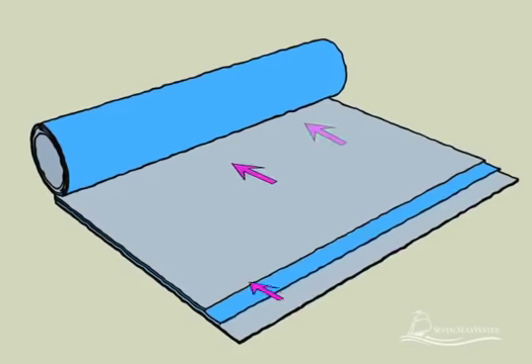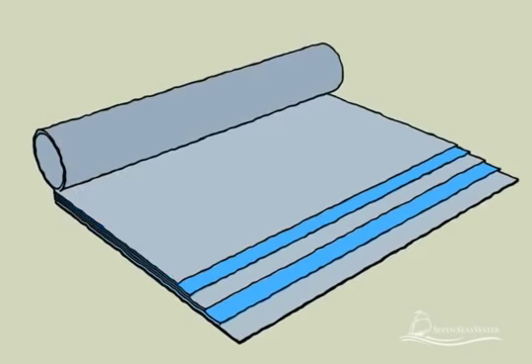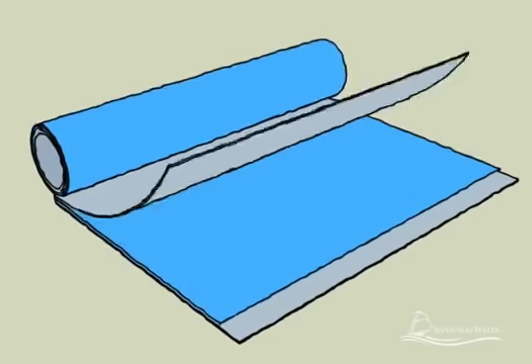The reverse osmosis membrane can be thought of as a number of sealed envelopes connected at their open ends to a tube. There are spacers between each envelope, which allow water to flow across the membranes. The membrane envelopes and spacers are then wound around the tube like a roll of paper towels.